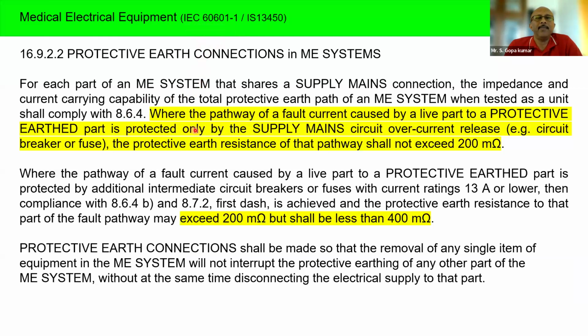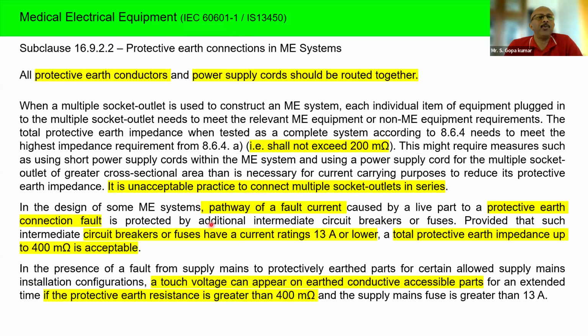There is an IS standard. The standard very clearly explained. For example, if the fuse is 13 amps, the impedance should be 200 milliohm. And if the impedance is more than 200 milliohm, then the standard says there can be a touch voltage. So this part I am just skipping. If you want, I can share the screens later on.